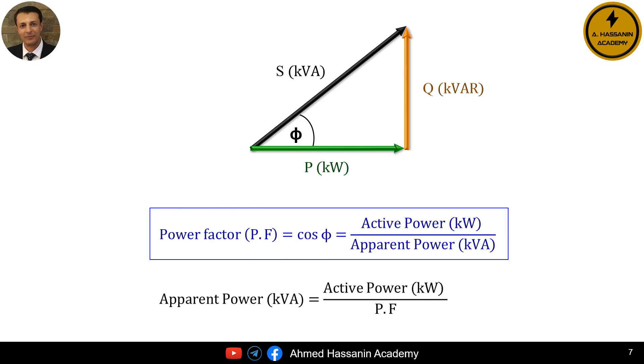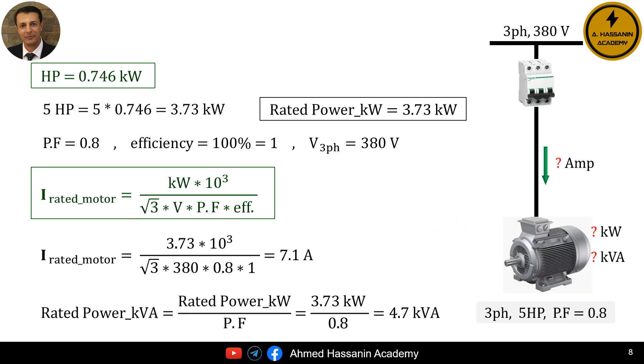Using the power triangle, we know that the power factor, or cosine of phi, equals the active power in kilowatts divided by the apparent power in kilovolt amperes. Therefore, the apparent power in KVA equals the active power in KW divided by the power factor. To calculate the apparent power of the motor: the apparent power in KVA equals 3.73 kilowatts divided by 0.8. Therefore, the apparent power of the motor equals approximately 4.66 kilovolt amperes, or about 4.7 KVA.